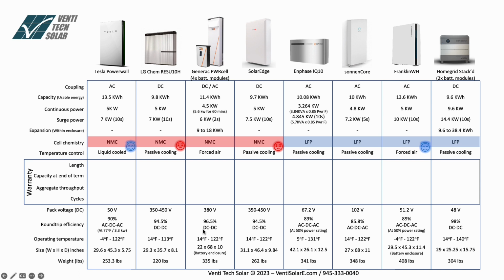96.5%, again DC to DC, and 94.5% on SolarEdge, DC to DC, 89% on AC, DC, AC. So 89% is what I'm expecting. It should be a standard for an AC coupled battery system or storage system, and that's because you have the AC conversion to DC and then back from DC to AC. So you see 89 for the Enphase is close to the 90% of the Tesla. It's different in there. The SonnenCore is probably the one that has the worst efficiency in there, also AC, DC, AC, and that depends probably on the testing mechanism they do. They probably are conservative on this number, or they tested it in real life scenarios instead of perfect conditions. So I give it to them for putting it at 85.8% efficiency.